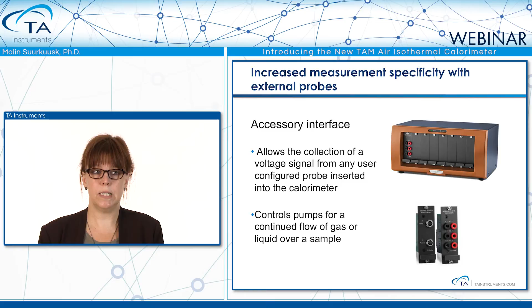I never mentioned it, but TAM stands for thermal activity monitor, so we measure the thermal activity of a sample inside the calorimeter. TAM Air, I said, is a microcalorimeter, but we can go up to milliwatt ranges in measuring. So it's a sensitive calorimeter. It has a temperature range up to 90 degrees. It's flexible in the sense that you can change the calorimeter block inside the thermostat. You have different sample sizes you can use, and you have a 3- and an 8-channel calorimeter.